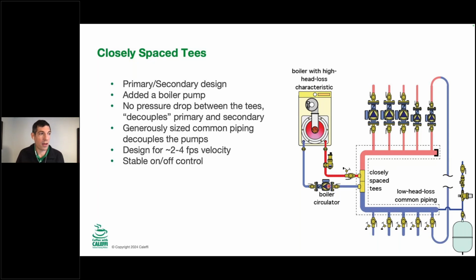And one of these things that I'll show a couple examples of, or kind of narrate as we go through, would mean if you took a balancing valve, a flow meter, that you could pull a pin like our quick setter and see what the flow rate is. If all 5 of these pumps are running and it's truly primary, secondary piping, closely spaced T's installed, as I'll describe on the next couple slides, you would see 0 GPM going through the boiler. That's how it should work. That's how it should work with all of these different scenarios, and that's how you can test it.